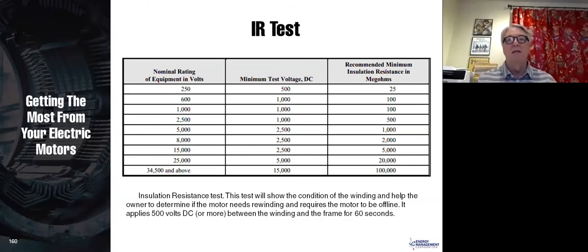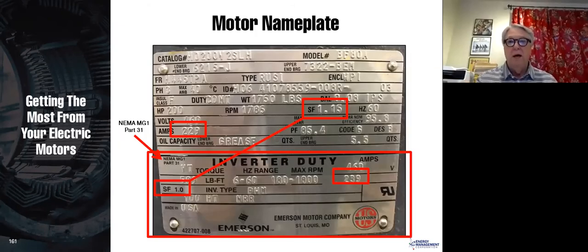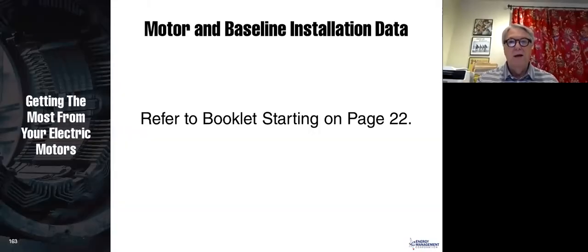Here's some testing. That's an IR test. It tells you what your minimum test voltage is, minimum insulation should be on a motor. There's your motor nameplate again. This is motor baseline. I'm not going to cover this much because you may or may not have that booklet in front of you, but on page 22 of that booklet, it gives you all of the things that you should write down anytime you start a motor.